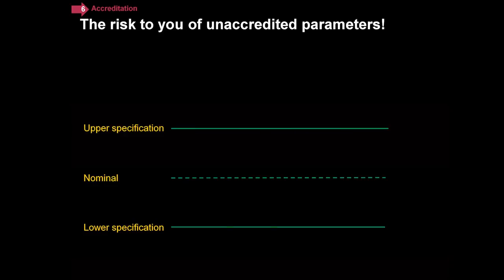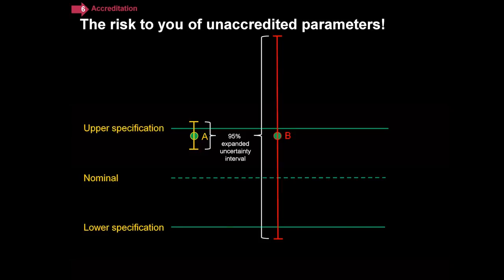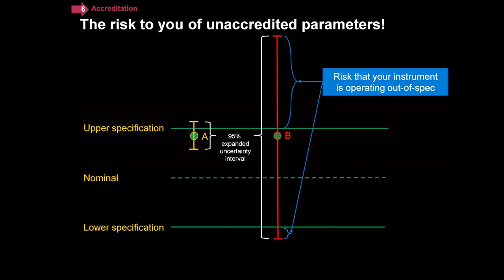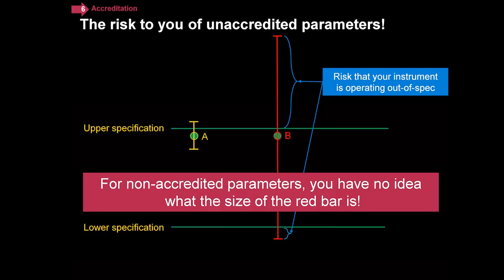I want to show you why I make the claim that this is very important. Let's look at two measurements — calibration lab A and calibration lab B. There are two different measurement uncertainties associated with each. The 95% expanded uncertainty is quite a bit smaller — that's the interval over which the true measurement could be. The true measurement in lab B could be largely outside the upper specification, and there's even a region outside the lower specification. If you're getting a calibration from a lab doing non-accredited parameters, you have no idea how large that red bar is.